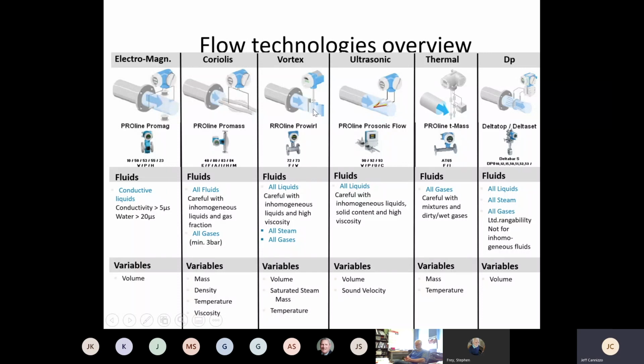Vortex meters, again, are volumetric meters, clean liquids and gases. They will do saturated steam. Today we have introduced, actually within the last year or two, pressure compensation as well, so we can do superheated steam and actual gas density calculations within the vortex meter. So you can get a true mass output for superheated steam and gases as well with pressure compensation. Ultrasonic meters, typically again clean liquids, some solid content. They are volumetric meters, and today we can do gas flow with ultrasonic meters as well.